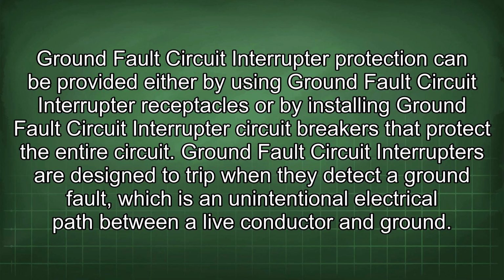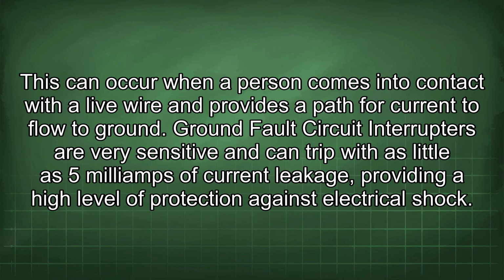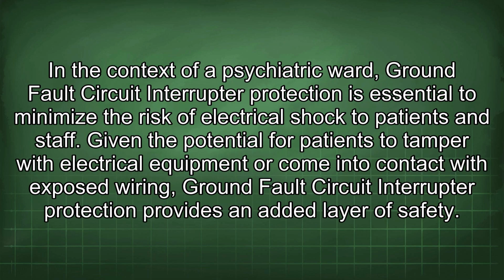Ground fault circuit interrupters are designed to trip when they detect a ground fault, which is an unintentional electrical path between a live conductor and ground. This can occur when a person comes into contact with a live wire and provides a path for current to flow to ground. Ground fault circuit interrupters are very sensitive and can trip with as little as 5 milliamps of current leakage, providing a high level of protection against electrical shock. In the context of a psychiatric ward, ground fault circuit interrupter protection is essential to minimize the risk of electrical shock to patients and staff. Given the potential for patients to tamper with electrical equipment or come into contact with exposed wiring, ground fault circuit interrupter protection provides an added layer of safety.